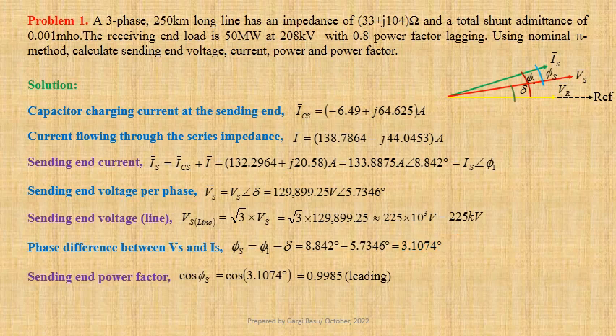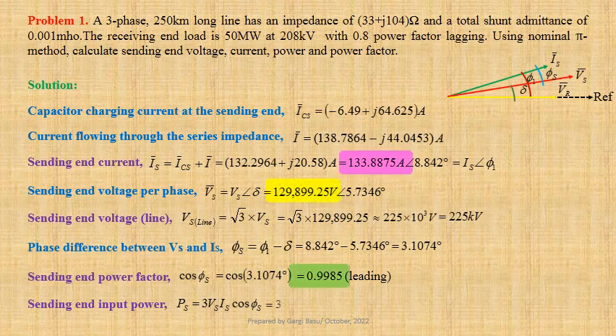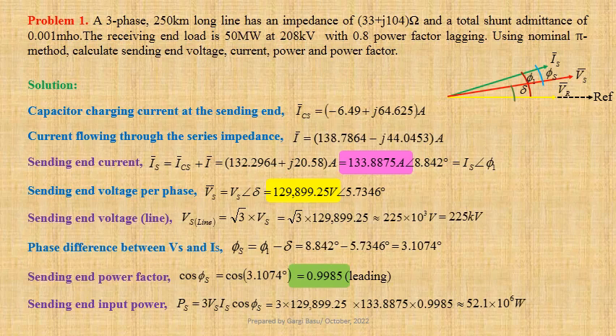Now we shall compute sending-end input power. PS equals 3 × VS × IS × cos φS. Using values we get 3 × 129,899.25 × 133.8875 × 0.9985, which is approximately equal to 52.1 × 10⁶ watts, that is 52.1 megawatts.